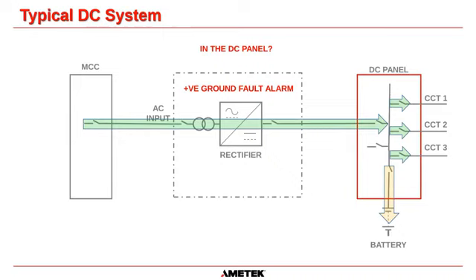And the last one is in the DC panel. So we've said the charger is okay, we've said the battery is okay. It has to be one of these circuits. And unfortunately, at that point you have two options. You can either isolate each load until the fault goes away, and then you know that the load that you isolated that clears the alarm has the fault. Obviously, to do that, you're going to be de-energizing your load circuits, which is never usually a good thing. But if you're in a position where you can do it in the plant, that is by far the easiest way to do it.